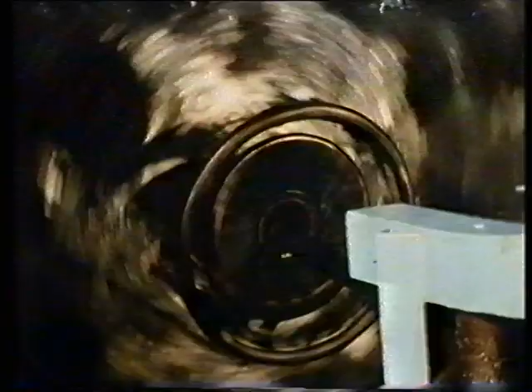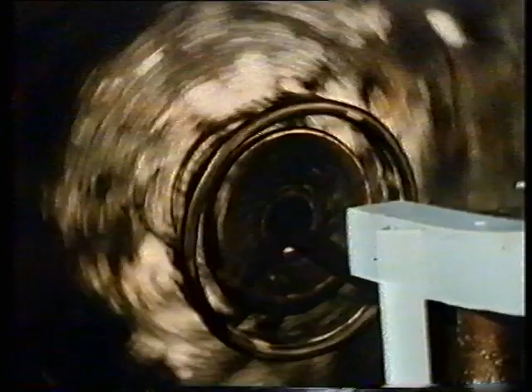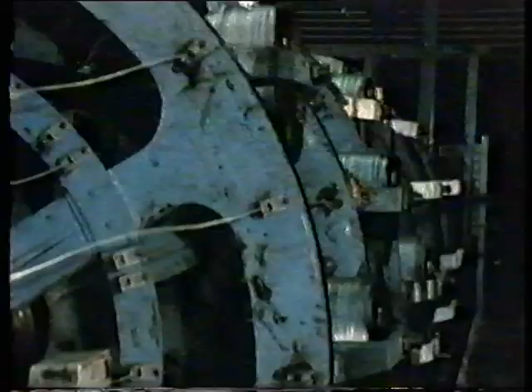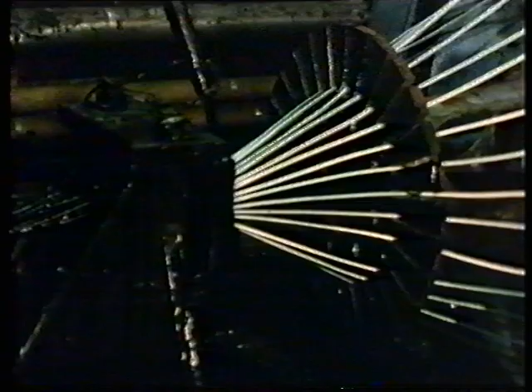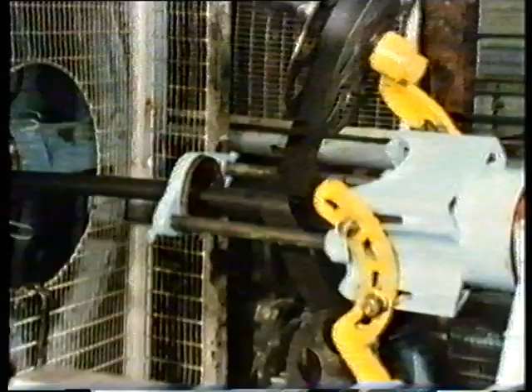First, a bedding of jute is applied to provide a firm foundation for the armor. The galvanized steel is 6 millimeters in diameter, and there are 26 wires in this first layer. As they're wound on, a bitumen compound seals them in and fills the space.